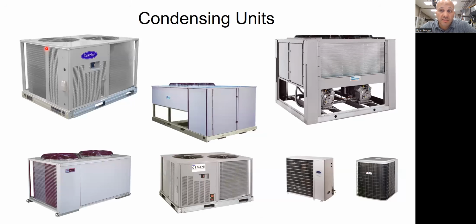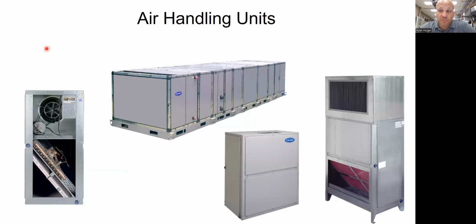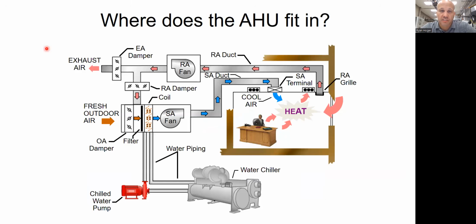But if you see one of these somewhere in the building, there has to be one or multiples of these doing the air handling side of the equation. We call it an air handler because it handles the air. We're not creative with the naming, but that means it has a fan and a cooling coil and possibly other stuff: heating system, humidifier, filtration, all those kinds of things. So where does this fit into the overall piece of the puzzle?